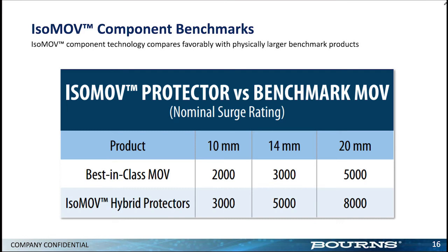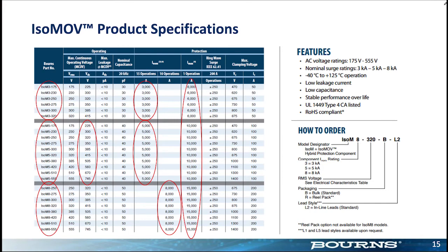All right, so this next question asks if you can elaborate on the lifetime and aging during transients. How many transients or surge cycles can it withstand? On the how many transient cycles, basically we follow the UL testing method, which has 15 operations of what we call the I nominal, and basically that 15 operations represent the life of the surge transient on those particular components. So if you look at the MOV, the PTVS, something like that following the UL, basically that 15 operations of the nominal current is what is considered the life of that component.